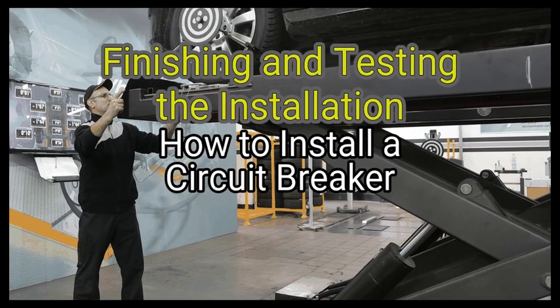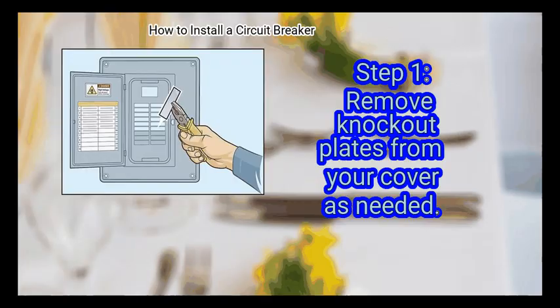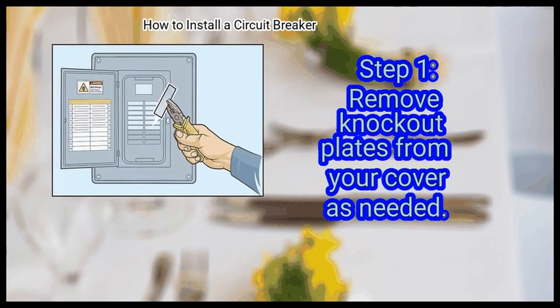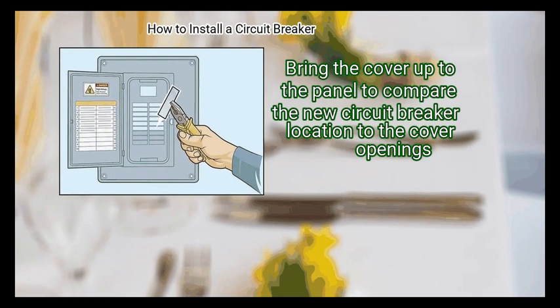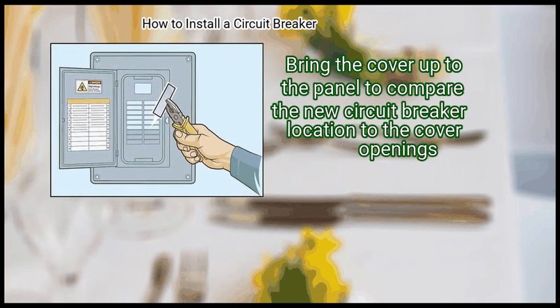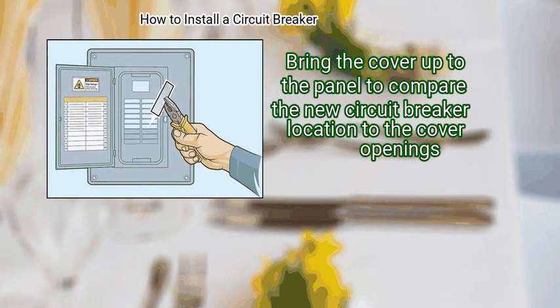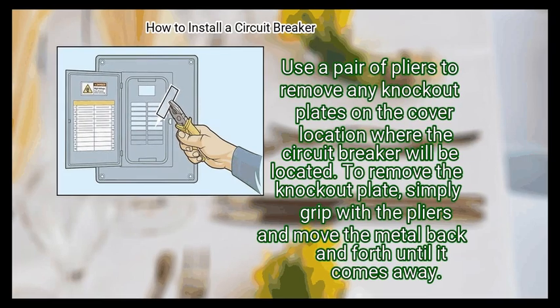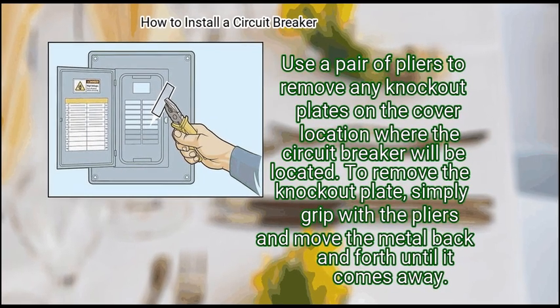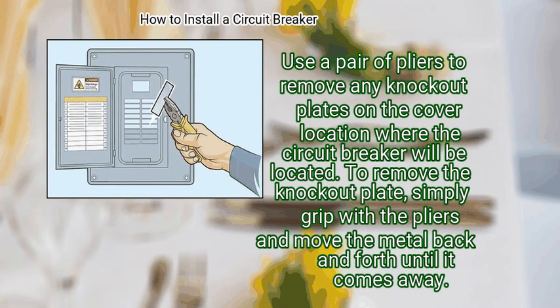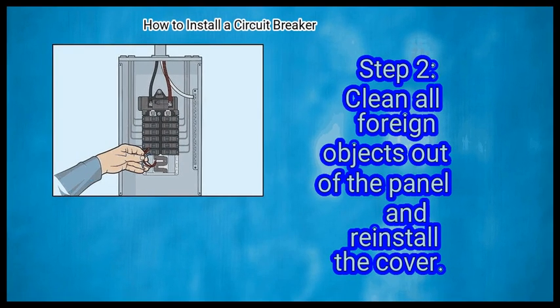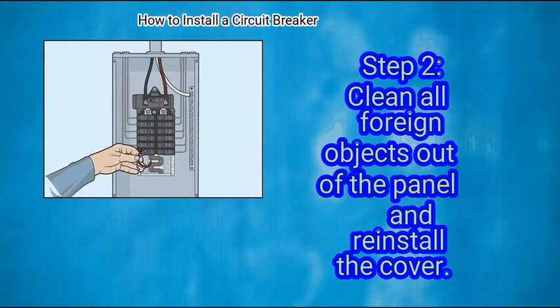Method 3. Finishing and testing the installation. First is remove knockout plates from your cover as needed. Bring the cover up to the panel to compare the new circuit breaker location to the cover openings. Use a pair of pliers to remove any knockout plates on the cover location where the circuit breaker will be located. To remove the knockout plate, simply grip with the pliers and move the metal back and forth until it comes away. Step 2. Clean all foreign objects out of the panel and reinstall the cover.